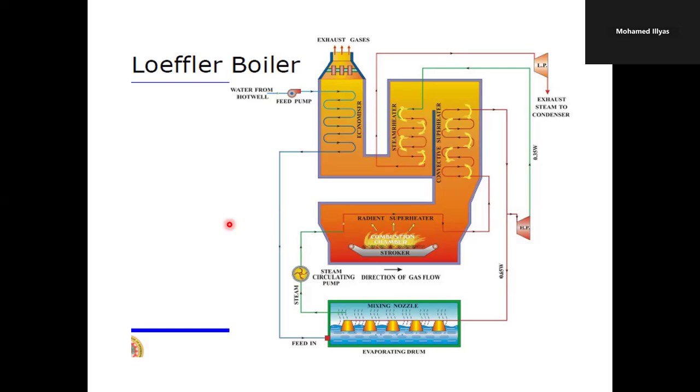But in the case of a Loeffler boiler, the arrangement is we utilize part of the steam for producing power, and the rest of the steam is utilized for heating the water. So around 65% of the steam produced in the boiler is used for heating the water, and the rest of the steam will be used for power generation purposes.